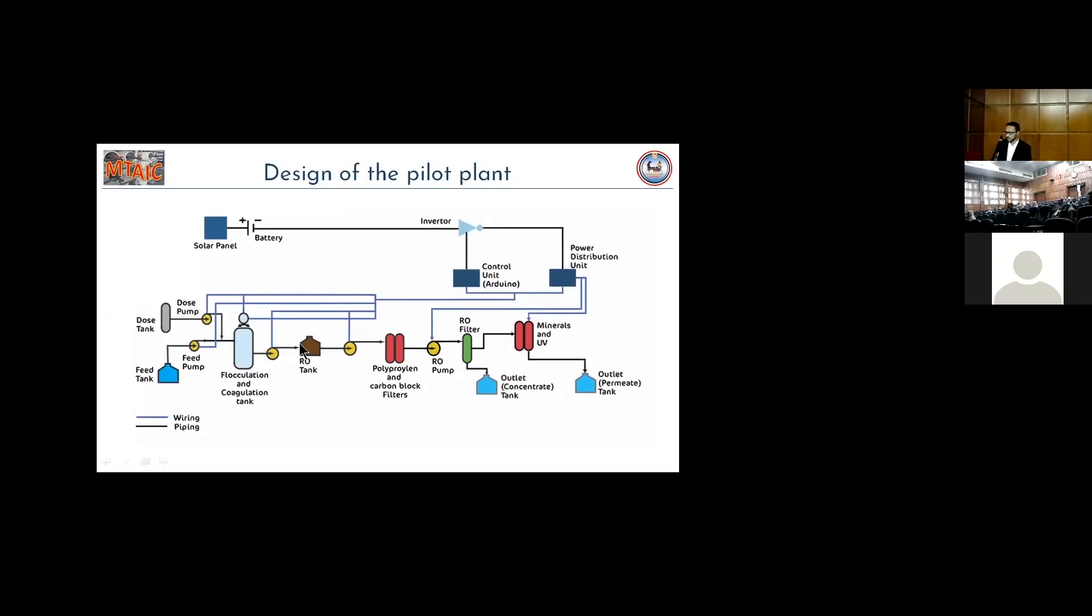After that, the RO tank will be partially loaded with water. And then the water passes through the multimedia filter of polypropylene and carbon block. Polypropylene to make sure that there is no suspended solid in the water, and carbon block to remove the chlorine that may harm the RO membrane if existing. Then the RO separates the feed water to the concentrate, and the low TDS water to permeate that is used in the irrigation.